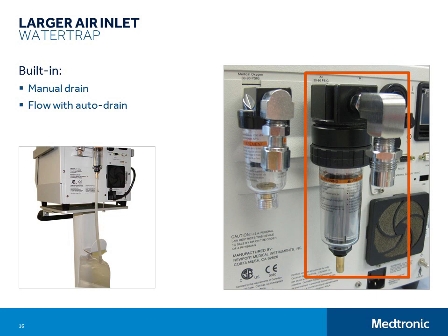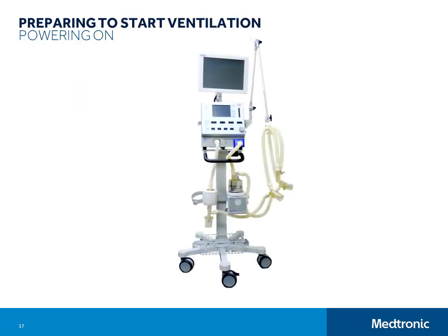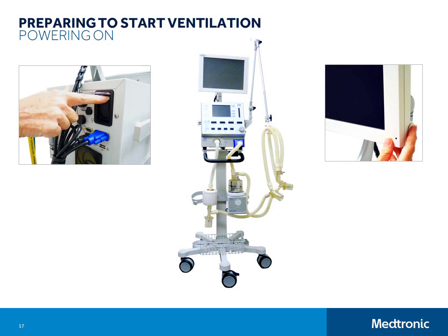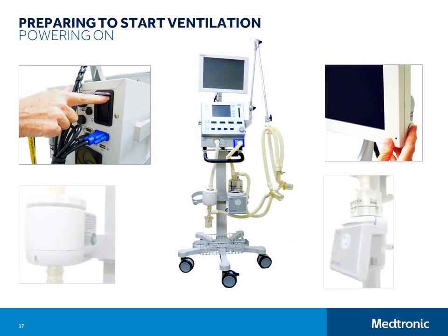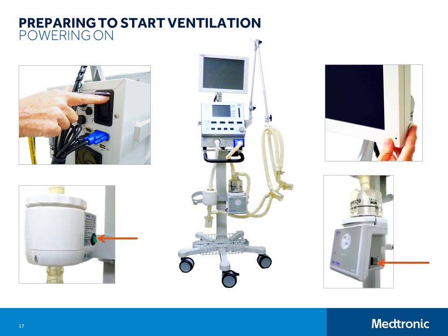After power and gases are connected, use the power switch on the rear panel to power the ventilator on. The E360 powers on with all of the same settings that were in place when the ventilator was powered down, except the non-invasive selection that always reverts to off. Electrical accessories have their own power switches, so make sure to turn them on as well when the time is right. If you are using a heated humidifier, you will need to fill the water chamber to the appropriate level before powering it on. Remember that you can prepare the ventilator in advance of patient arrival so that it can be ready to go the second the patient arrives.